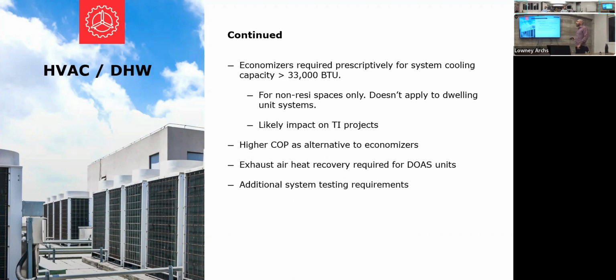So what we were seeing, for instance, with old buildings, VRF is a very popular system type, or you can put split systems sometimes when you're renovating old buildings. And that was okay in the past. Now, if you have those systems where the capacity of each equipment is greater than 3 tons, then you have to provide either an economizer or a dedicated outdoor air supply to those zones with economizer capability. So it made it a bit more complicated.